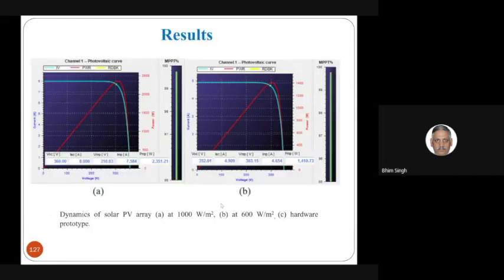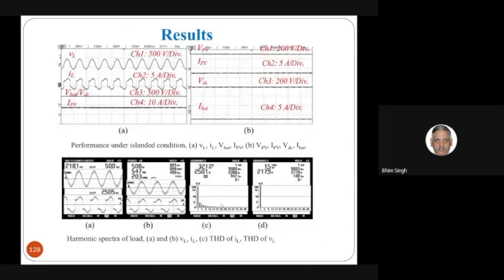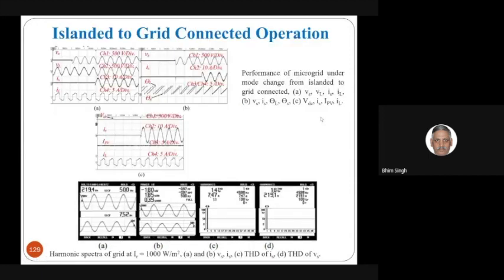It works on MPPT for different solar insolation levels, at 1000 watt per meter square as well as 600 watt per meter square. And this is a typical result where you can clearly see it in islanding mode. It is feeding a highly non-linear load with 32.1% THD, but still the voltage at the point of common coupling is 1.5%. So it is feeding the non-linear load in islanding mode with solar power generation there, and the remaining power goes to the battery.